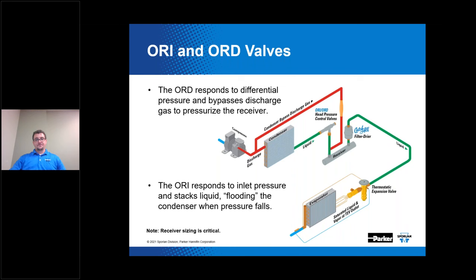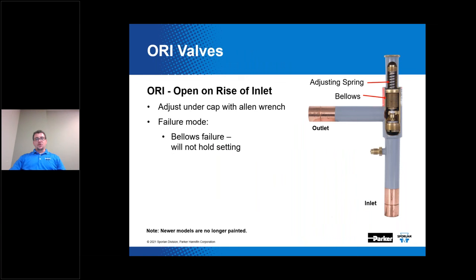The ORI is an adjustable valve with an adjustment range of 65 to 225 PSIG. It has a flexible bellows above the seat disc. The outlet pressure is exerted on the underside of the bellows and the top side of the seat disc, and because the effective area of those bellows equals the area of the port, the outlet pressure is canceled — allowing the inlet pressure, or condensing pressure, and the spring pressure to be the two operating forces controlling the position of the ORI. We do offer spring kits for the ORI with a larger range of adjustment from 100 to 290 pounds.